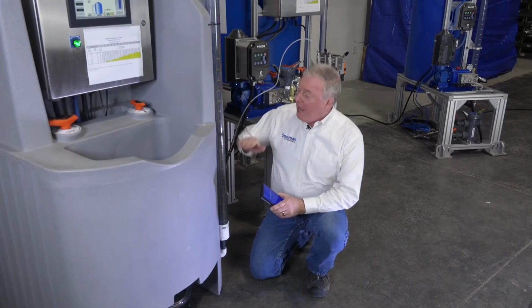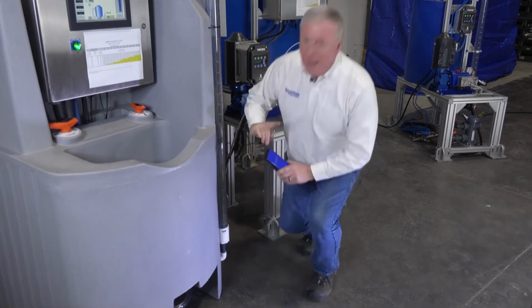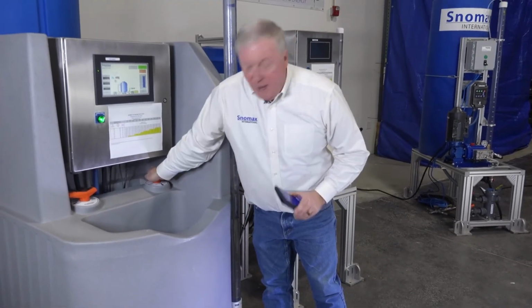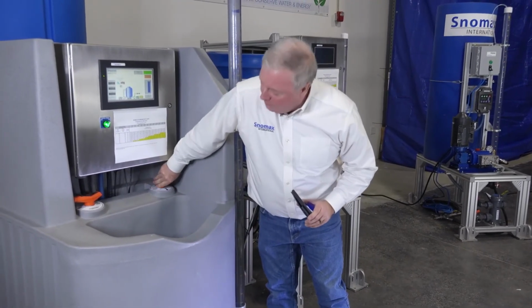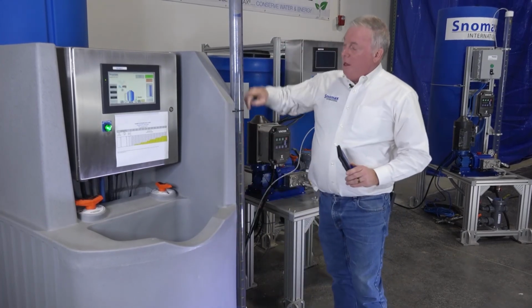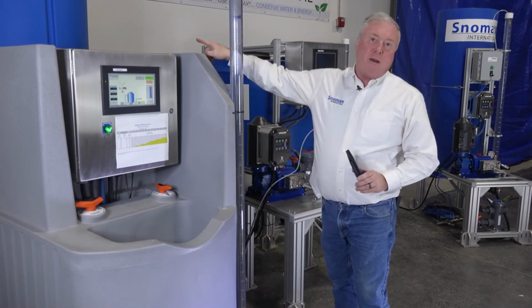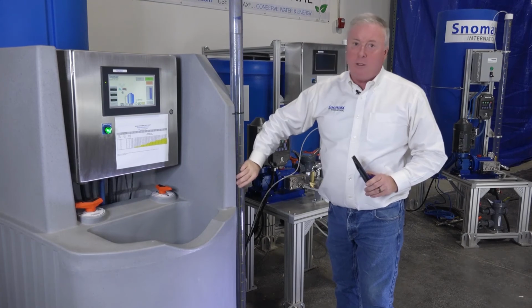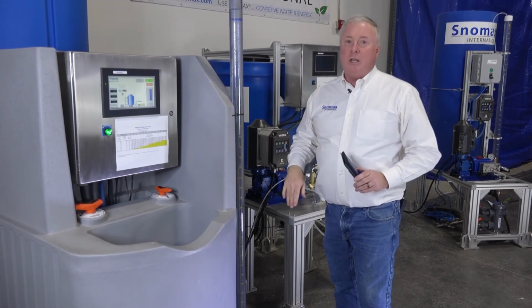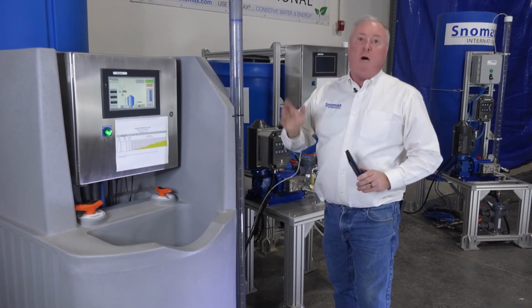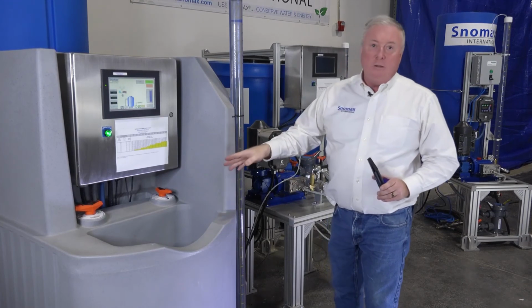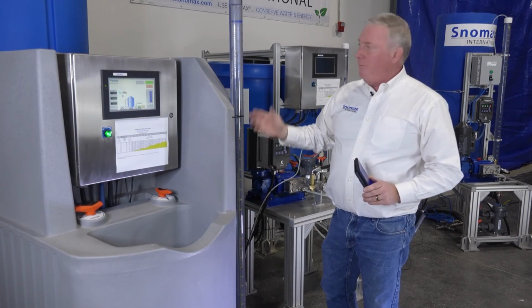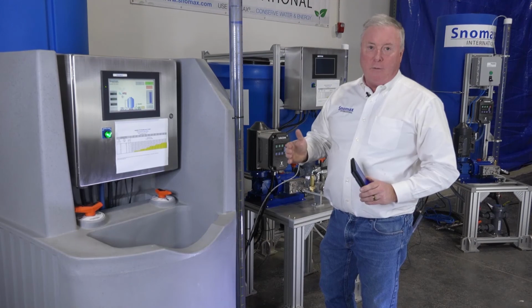So one thing to remember is after you're done doing the calibration, don't forget, you've gotta put this valve on all of our systems back in its resting state. Otherwise, you're not pumping out of the tank anymore, you're only pumping out of here. When this runs dry, the Snomax injection stops. So it's really important on all three of our systems to make sure to reopen the valve that separates the tank from the calibration tube.